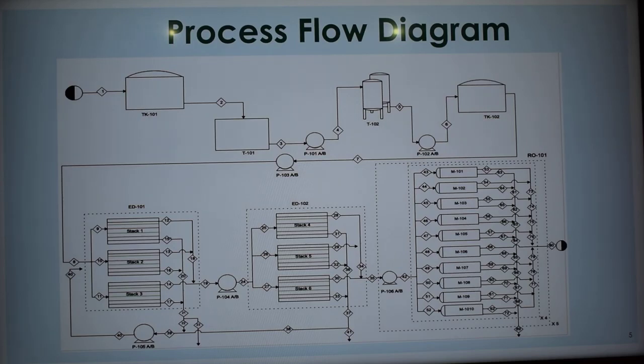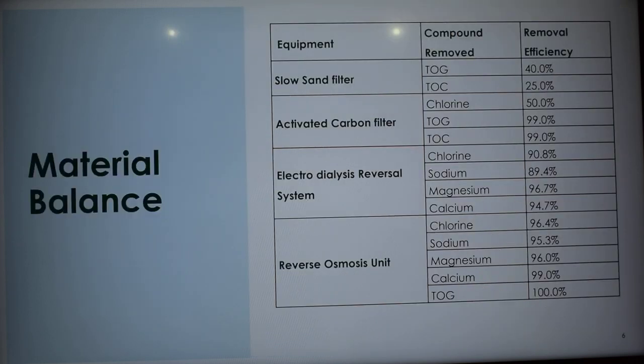And then from that storage tank, the water flows to EDI unit, with a flow of 150 meter cube per hour. The water flows from EDI unit 1 to EDI unit 2, and the final product from EDI unit 2 goes to reverse osmosis unit. But in order to increase the production, we recycle 40% of the waste stream from EDI unit 1 and EDI unit 2 so that we have a higher production. And then from reverse osmosis, the reject stream is being sent for further treatment, while the permeate stream is sent for cooling tower. Next is the material balance for all the equipment that we have used.